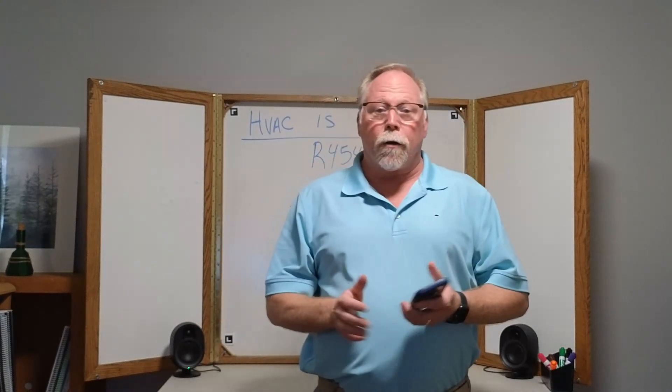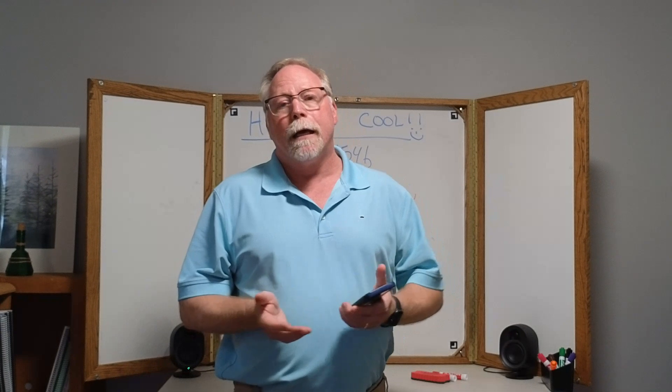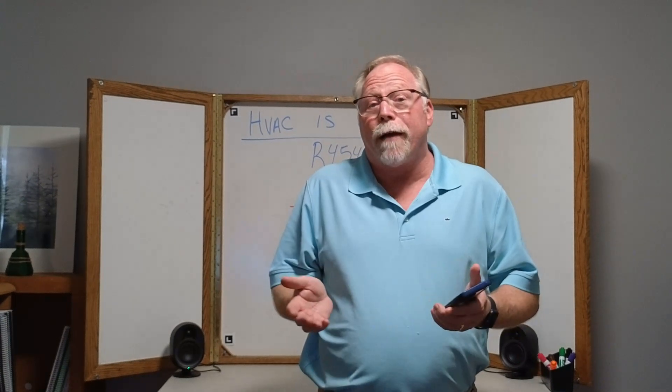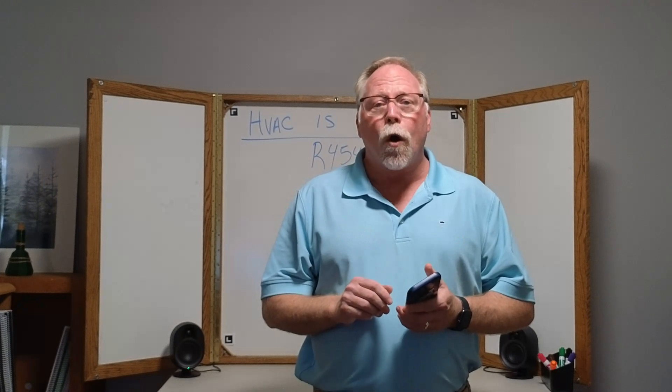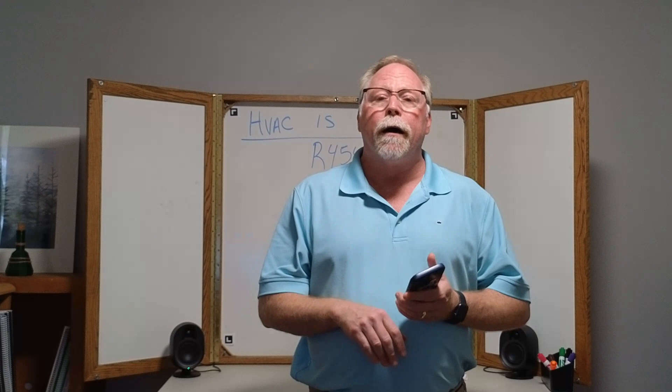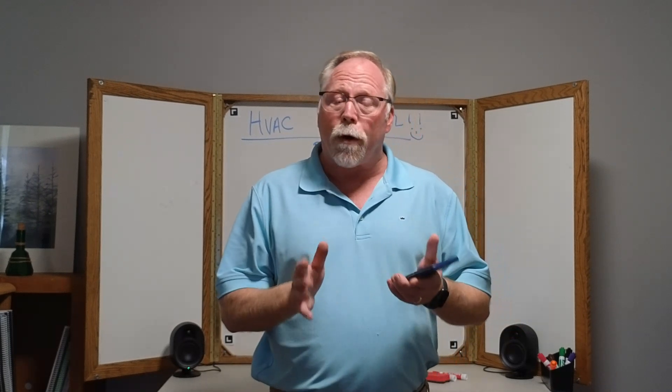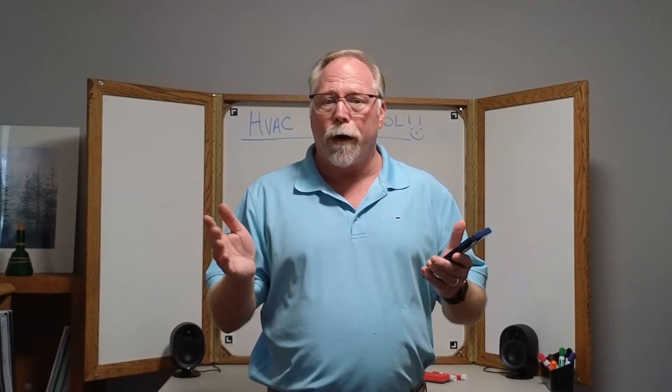Okay, hey everybody, this is JoJo the HVAC Man. It's been a while since I've seen you. I've been quite busy, but I wanted to do a new video here. It's not going to take long, but it's simplifying, I believe, the dew point and the bubble point for R454B. Dew point and bubble point's been around for a long time, but we really haven't had to worry about it. R22, R12, they didn't have any glide. R410A had a minimal, negligible glide which was a near azeotrope, acted just like the rest of them.